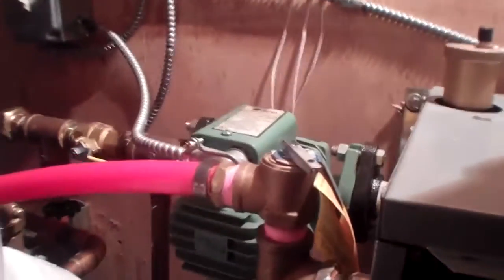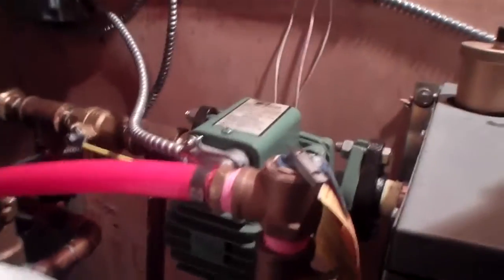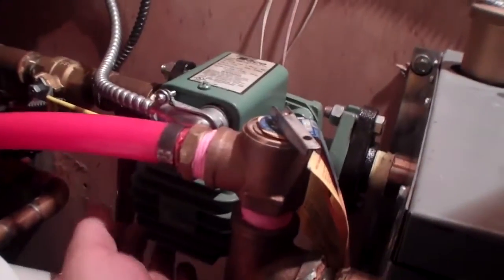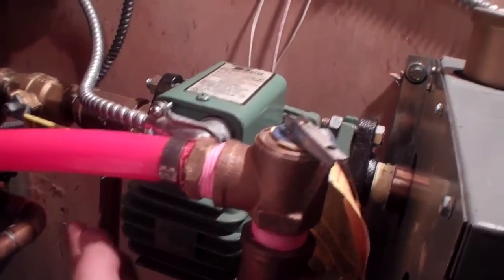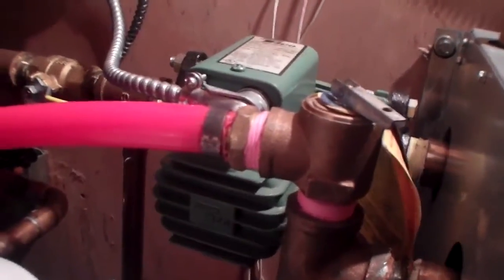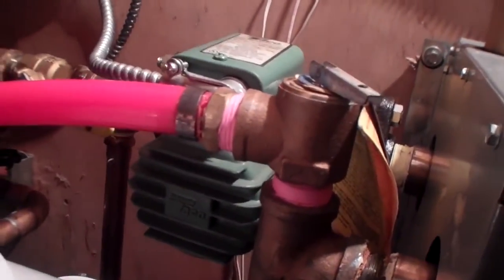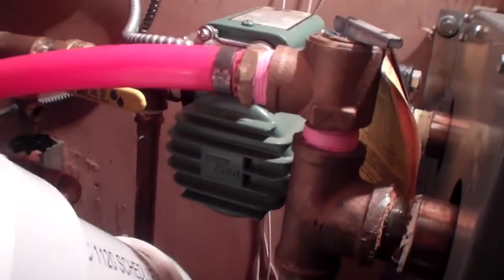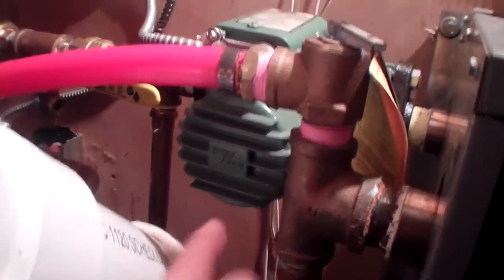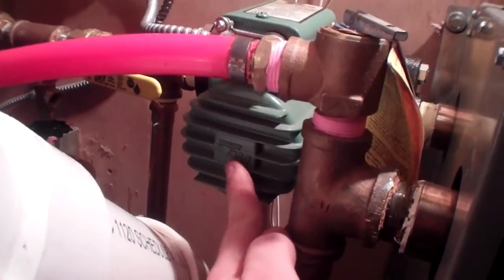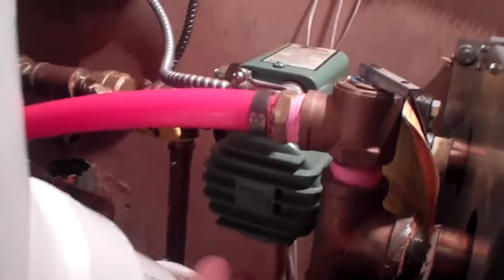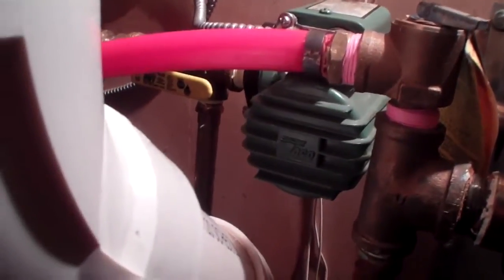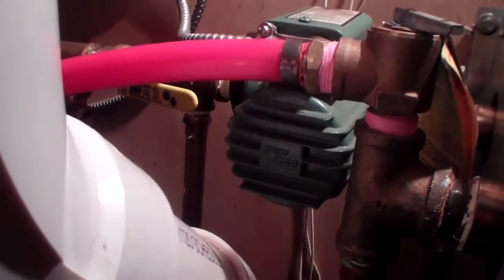The other thing I want to note too about this system is that you really, really, really, I can't stress it enough, you've got to make sure this pump's working. Because if this pump's not working, you're not getting any hot water when your domestic hot water is called. So these things have a tendency sometimes to lock themselves up. So you actually have to pull the pump out, pull the impeller out, and free it with your hand.